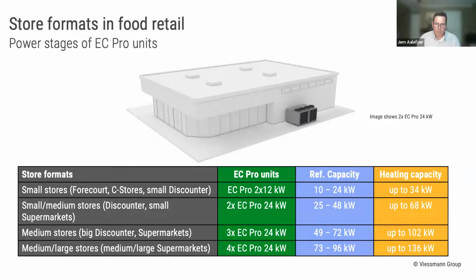The store formats we are supporting mainly are small stores, what we call forecourts, convenience stores, small discounters, small and medium. You see here we go up, we parallel them upwards. Medium stores, big discounters, supermarkets, and medium large stores, which gives a capacity up to 96 kilowatts in cooling and 136 kilowatts in heating. There's actually no theoretical limitation. We can parallel more than we do here, but the price difference adds up there. So in essence, this has been where we have found our sweet spots in installations. However, we can do whatever and how many you want. There's no real limitations to how we can do this.